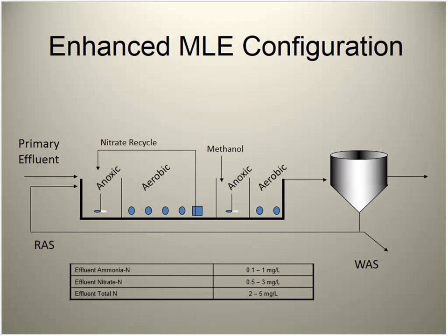The enhanced MLE duplicates the anoxic and aerobic sections — doing it twice to ensure a sufficient carbon source. Methanol or a proprietary carbon source like micro-C is added. A final aerobic zone ensures no denitrification carries into the clarifier. The modified MLE achieves effluent total nitrogen of 6–10 mg/L, while the enhanced version reaches 2–5 mg/L.